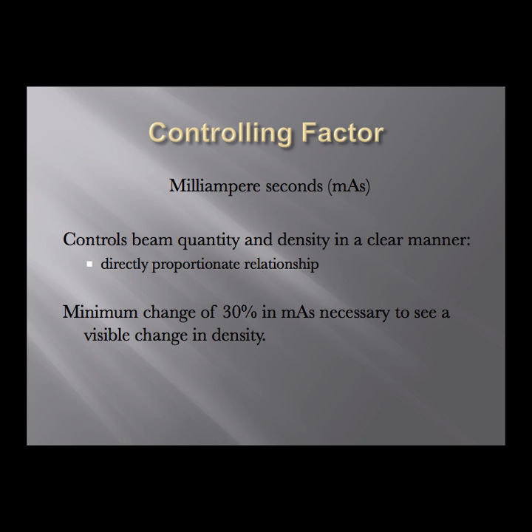One of the guiding rules for mAs is that in order to see any visible change on the film — for example, if you're doing two successive films on the same patient and the first one is too light — you have to go up at least 30% in mAs to see any visible change. The suggestion is to use values like half, twice, or three times as much mAs to make a substantial change. You don't want to go up just a couple of mAs at a time because you won't see any change from one film to the next.